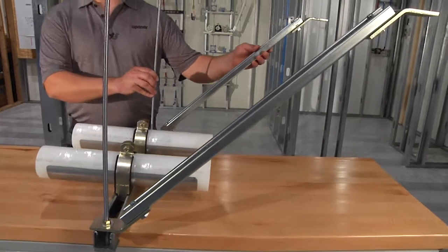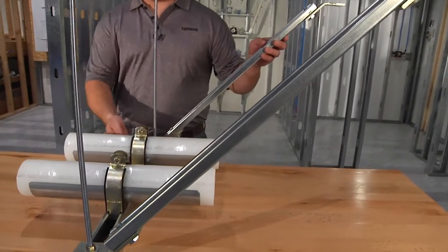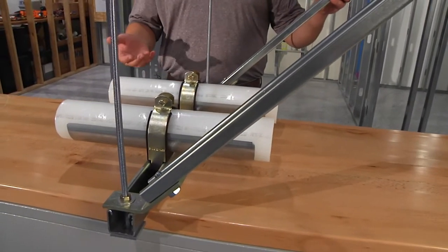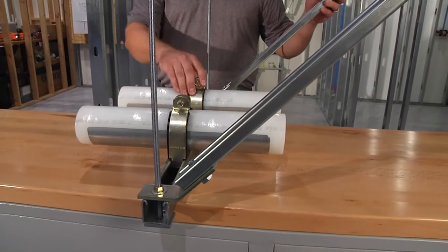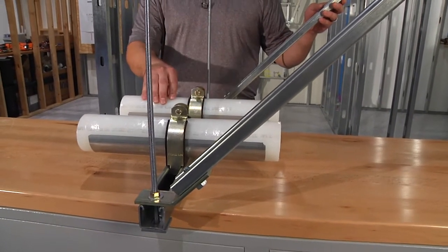A fixed anchor point is essentially triangulating a typical strut hanger, very similar to a seismic restraint, and using a rigid pipe clamp that's going to restrain the piping material itself.